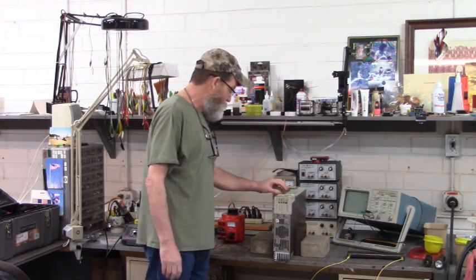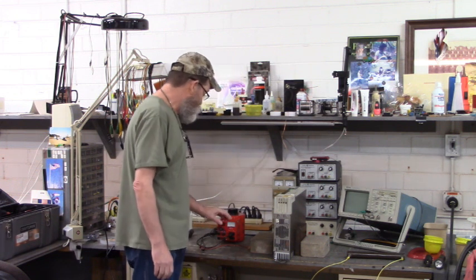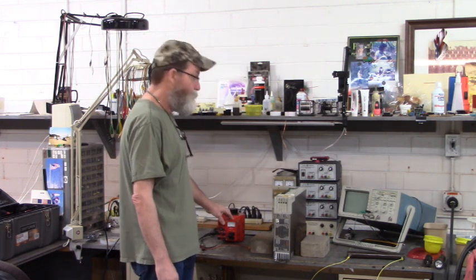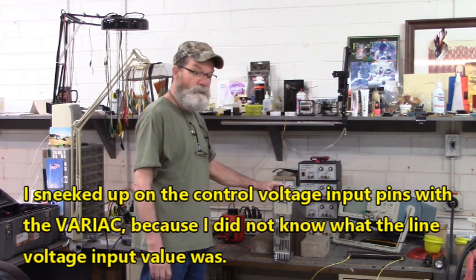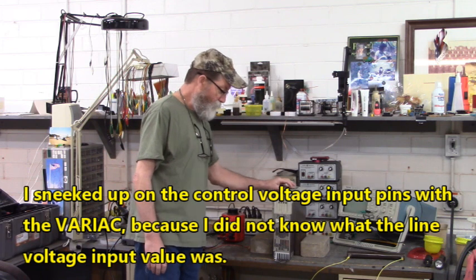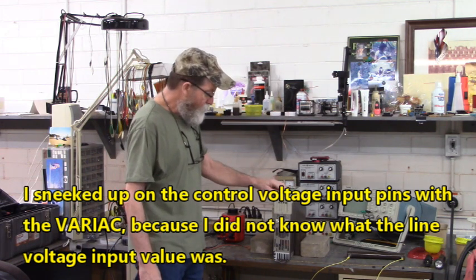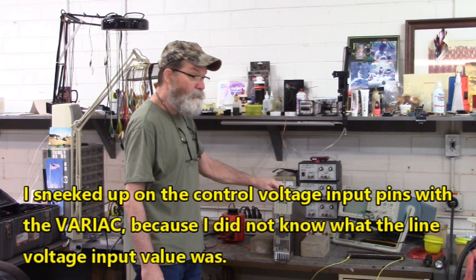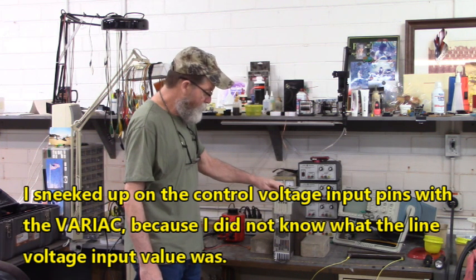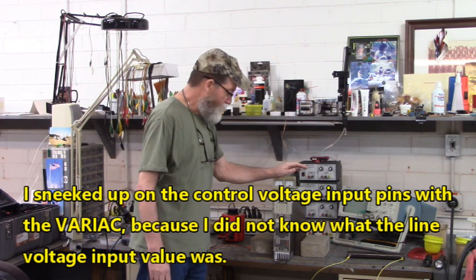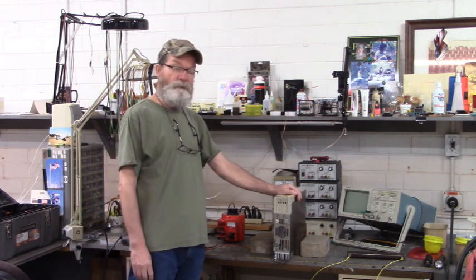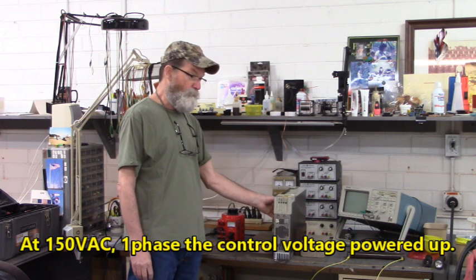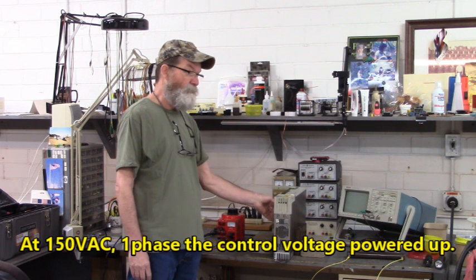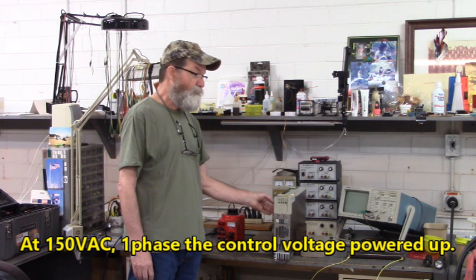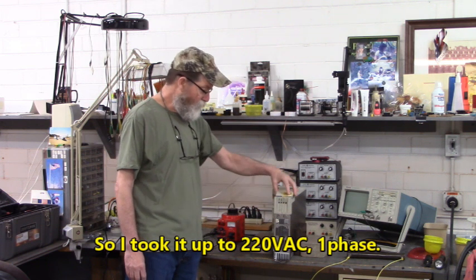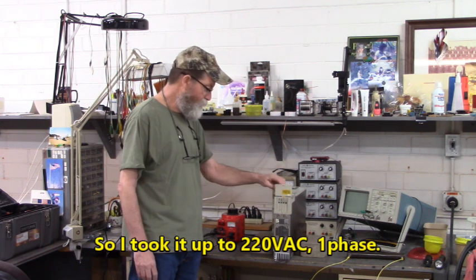But first, let's get it powered up. We're going to apply from this variac 220 volts AC single phase to pins 1 and 3 of this green Phoenix connector. Then we're going to apply 380 volts AC 3-phase to L1, L2, and L3. And here's the peculiar part: there's a DC contactor and it routes the output of the 3-phase bridge to these terminals up underneath this lid right here. You'll see them in a little bit.